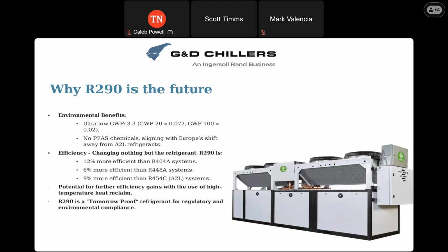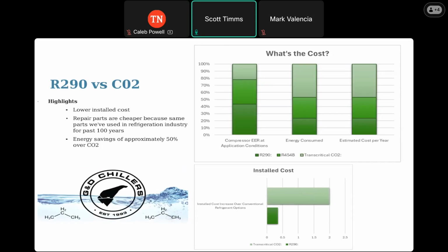We can move to the next slide. Essentially, when it comes to these low GWP solutions, people start looking at natural refrigerants for the future. There are three separate natural refrigerants we can speak to: R290, which is propane, CO2, and ammonia. Ammonia also has a very low GWP. The refrigeration cycle it uses is different, and it's also very toxic, so ammonia installations require really heavy SOPs and safety protocols. For relatively small scale breweries, it doesn't make sense at all; it's more for huge industrial facilities.